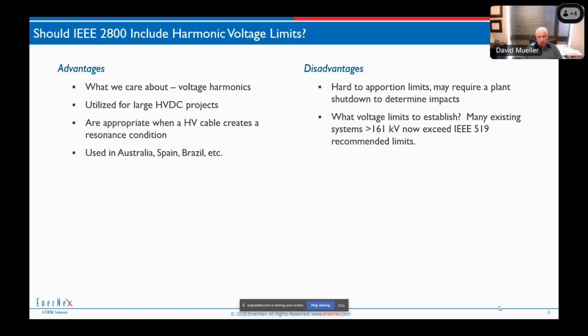So if we're already over the limit, are we going to ask our IBR plants to filter to get down to the limit, or how are we going to establish that? How are we going to determine what contribution the plant is making to the limits? Are we going to shut things off, turn things on? Harmonics are time varying, so it's very difficult to apply harmonic voltage limits.